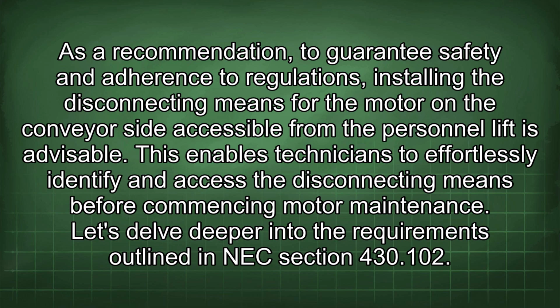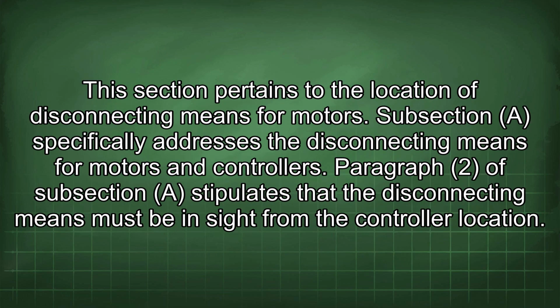Let's delve deeper into the requirements outlined in NEC Section 430.102. This section pertains to the location of disconnecting means for motors. Subsection A specifically addresses the disconnecting means for motors and controllers. Paragraph 2 of subsection A stipulates that the disconnecting means must be in sight from the controller location.